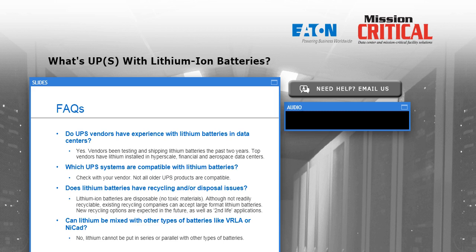Which UPS systems are compatible with lithium batteries? Can I throw them on any UPS out there? Better check with your vendor. We need to regulate the charge current to the lithium batteries very closely, and some older UPSs may not have the ability to limit the battery charge current. The battery charge current might vary with the load on the output of the UPS, so not all older UPS products will be compatible, at least not at the start. Do check with your vendor before you deploy a lithium battery with the UPS.